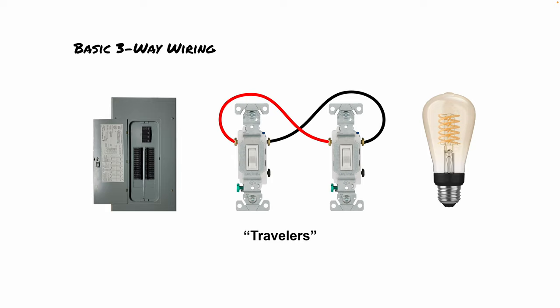Now let's talk about the travelers. Travelers go between the two brass terminals on both light switches and control the circuit to turn the light fixtures on and off. You typically have a red wire and a black wire going between the two switches. Sometimes, though, you'll have a red wire and a white neutral wire with black tape on it to indicate it's also used for power. Those are the two different types of traveler wiring you'll see.